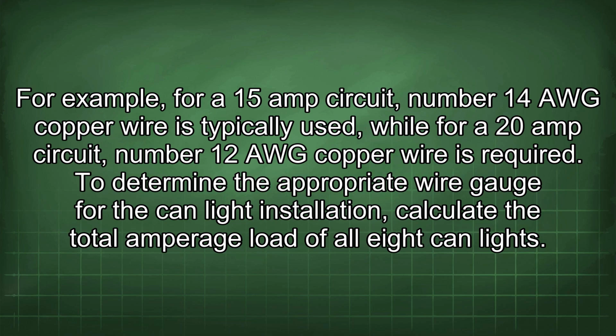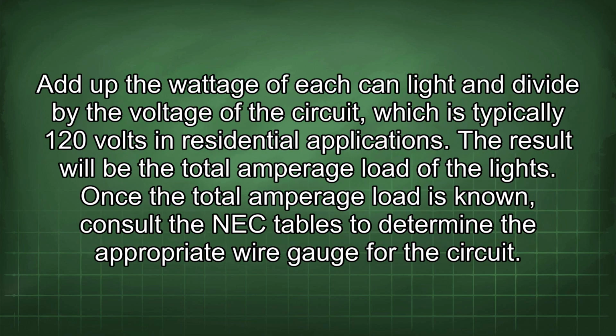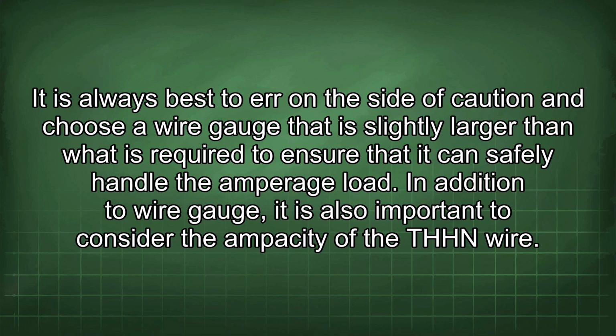To determine the appropriate wire gauge for the can light installation, calculate the total amperage load of all 8 can lights. Add up the wattage of each can light and divide by the voltage of the circuit, which is typically 120 volts in residential applications. The result will be the total amperage load of the lights. Once the total amperage load is known, consult the NEC tables to determine the appropriate wire gauge for the circuit. It is always best to err on the side of caution and choose a wire gauge that is slightly larger than what is required to ensure that it can safely handle the amperage load.